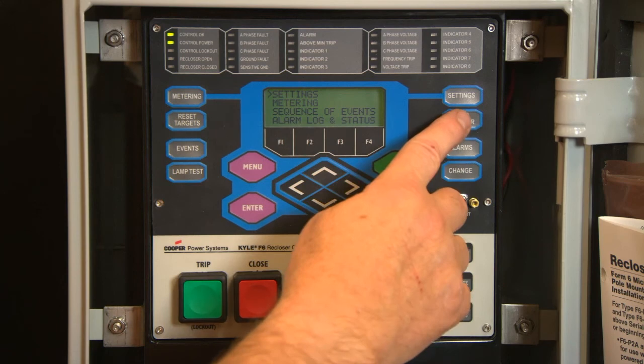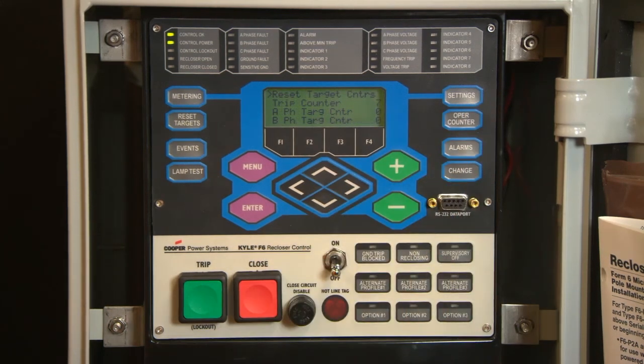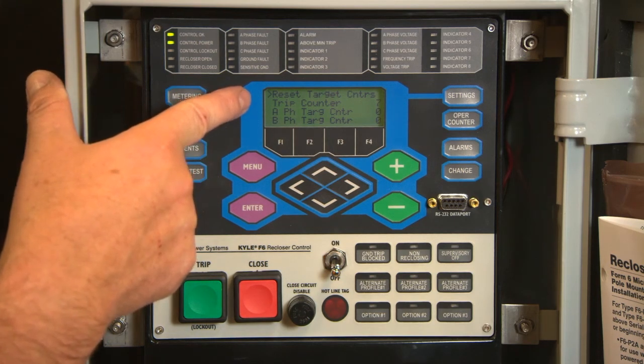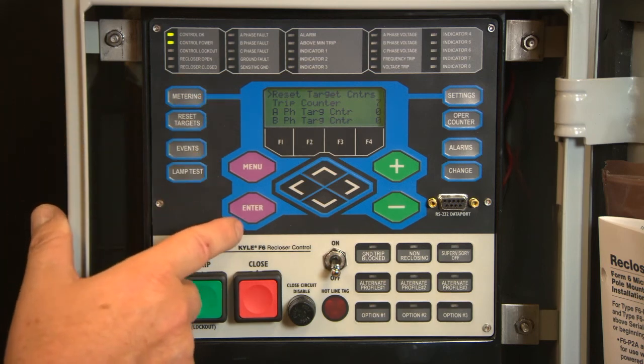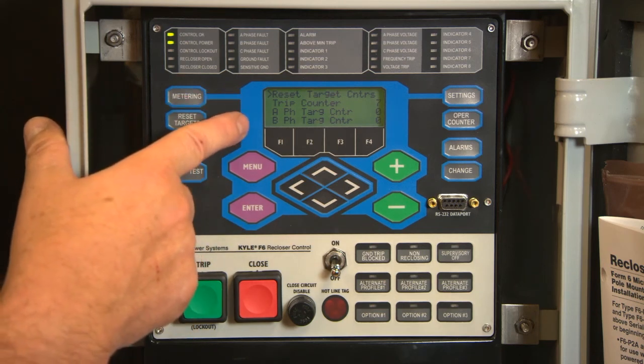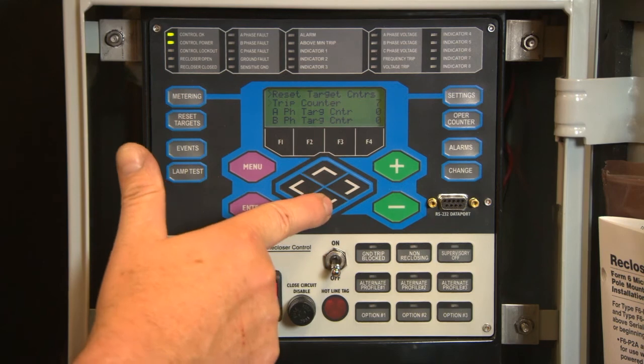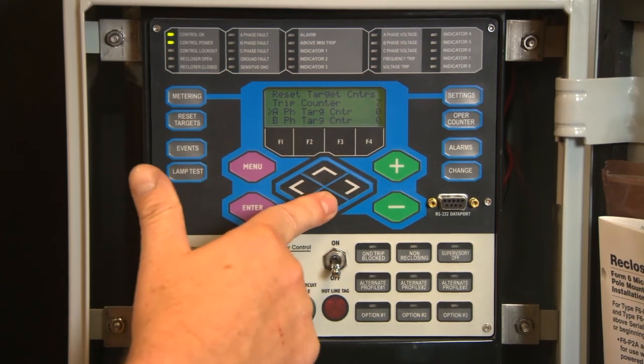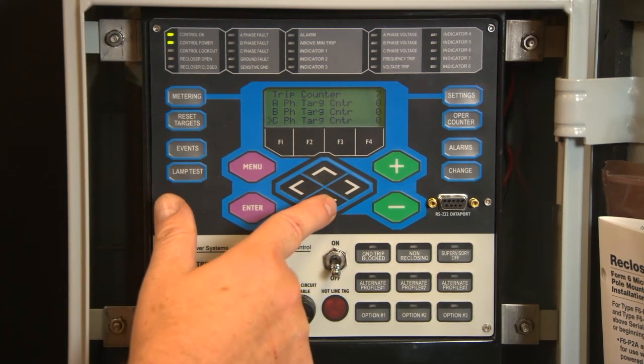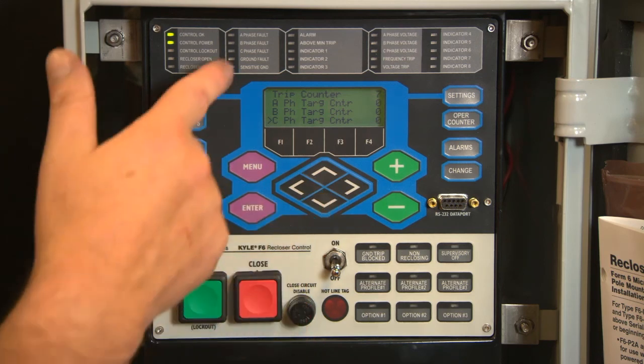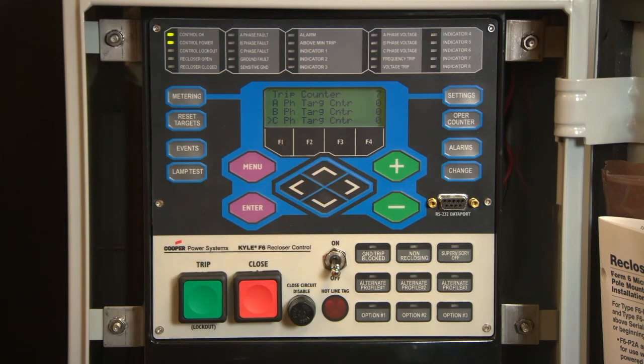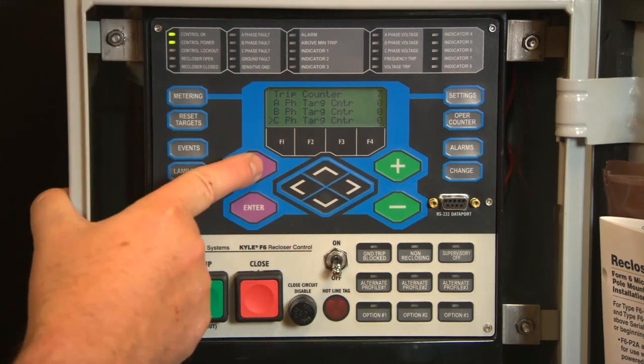Operating Counter. Pressing this button will display which phases have been tripped. At the top of the display is a trip counter. This currently reads 7. A phase and B phase both display 0. Scroll down to find the C phase. This will indicate how many operations each contact has performed on a faulted condition. Press the Menu button to return to the main menu.